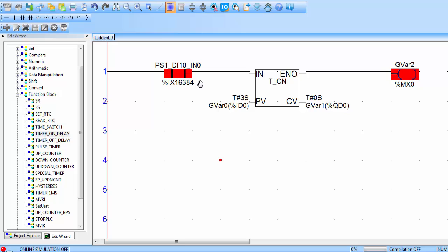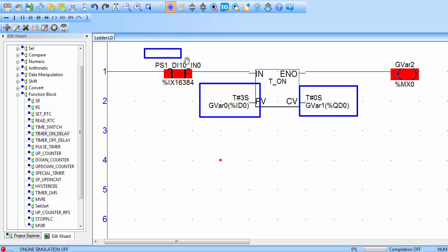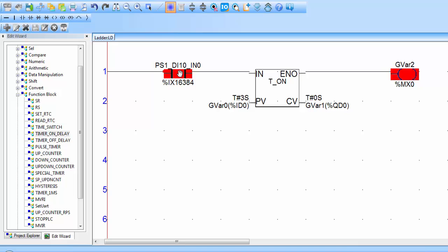Now for the initial condition, the preset value is set for 3 seconds, and you can see what is the current value. It is 0 seconds because the timer is off, that's why the current value is set to 0. To turn on the timer, we have to provide the input from this contact to the IN pin of the timer.